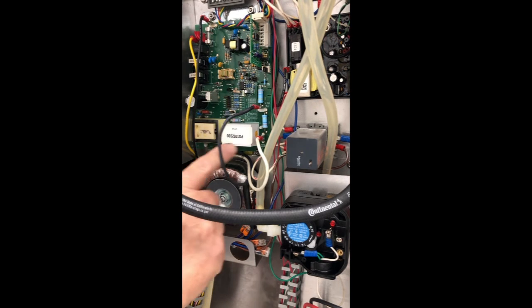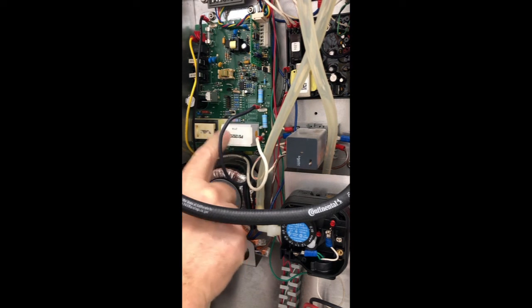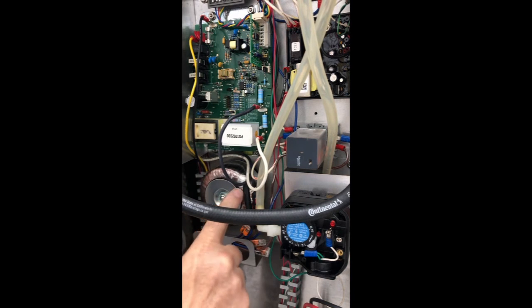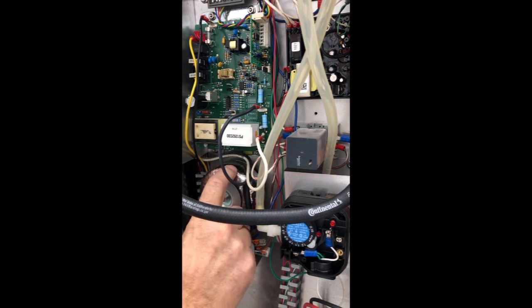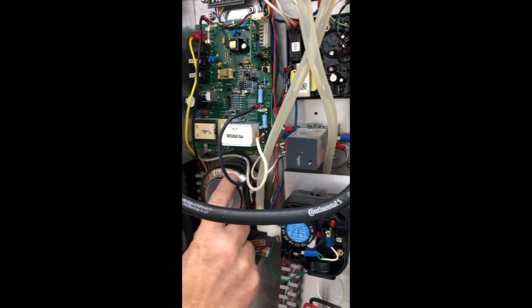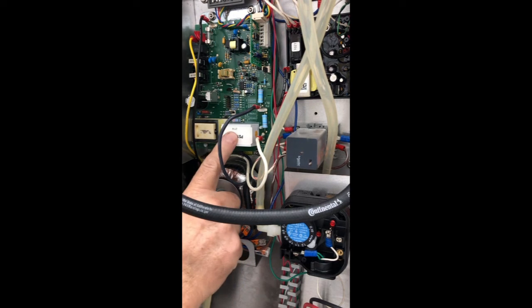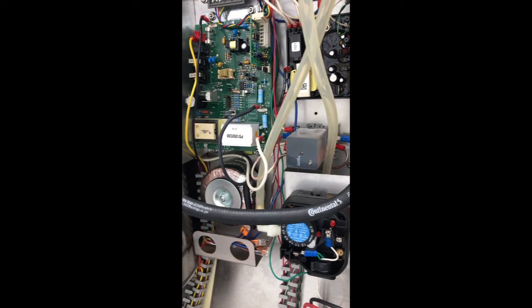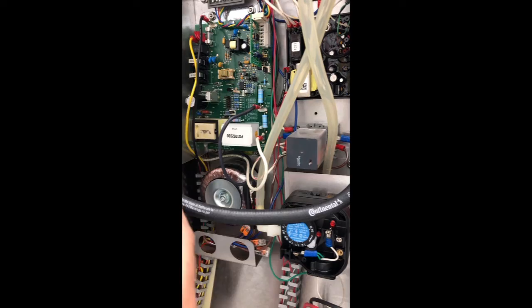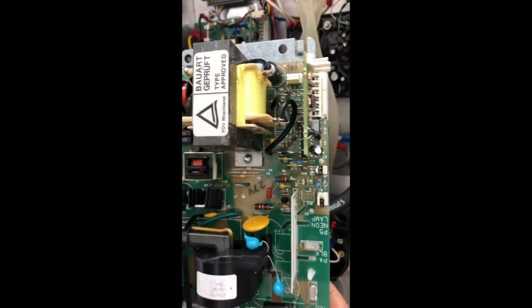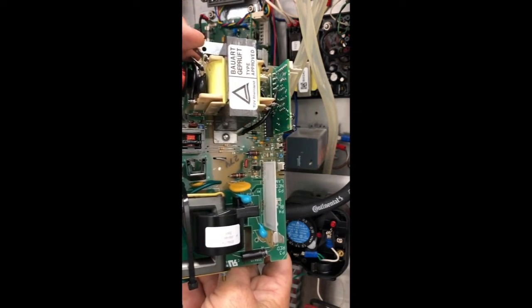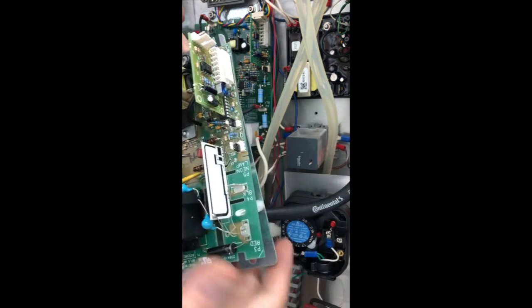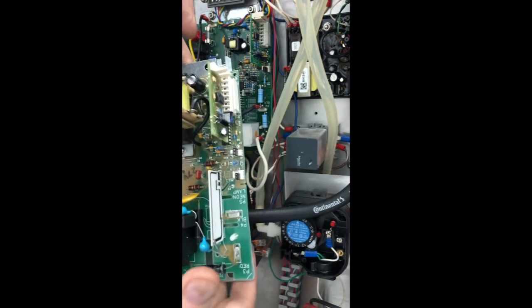Now this particular unit has the 120 volt board in it. That is the one that we currently use, and that is the reason for the transformer. The transformer that we talked about earlier only takes that 208, 240, knocks it down to 120 just for this one board. Now, if this board should fail and you have to change it, you may have one of these old style boards. Now on this old style board, P1 and P2 are actually these two terminals right here. So it says same voltage. You still have a P3 and P4 here. You do not have those jumper settings, so we don't have any real control.